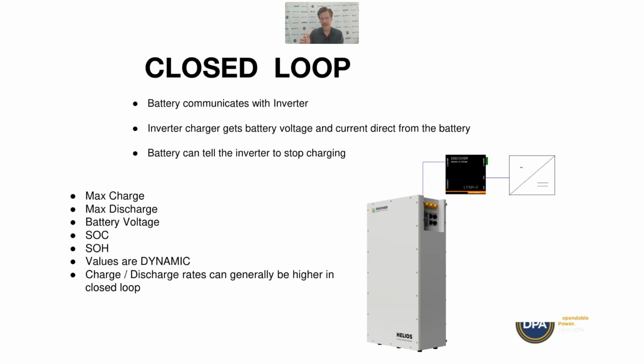These values are dynamic, so it's different to just setting it on the inverter, and it means that it can charge it at a higher rate when conditions are favorable, and then roll that back if the battery's hot or if it's getting towards the top of the charge cycle or towards the bottom of the charge cycle. If you don't have that dynamic communication, then you have to be more conservative with those settings.